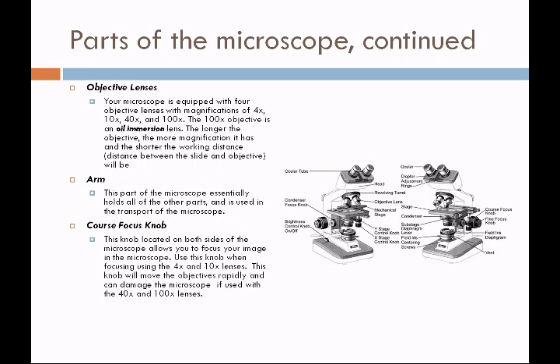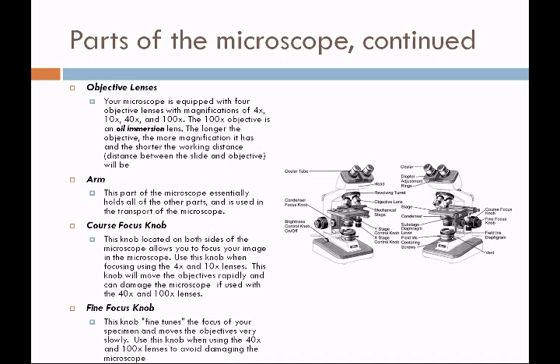If you are cranking the coarse focus rapidly, there's a risk that you could smash the slide or damage your objective if you are using a higher power objective. The fine focus knob is going to fine-tune the focus of your specimen and it moves the objectives very slowly. You want to be sure that you are using this knob when you are using the 40x objective and the 100x objective to avoid damaging the microscope or the slide.